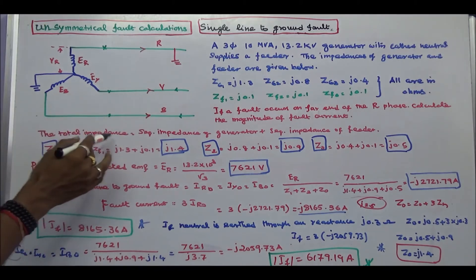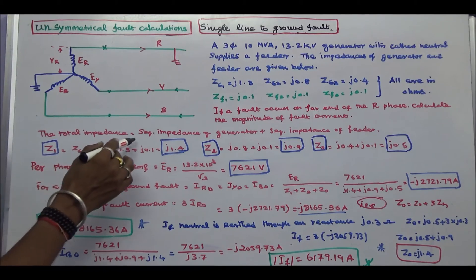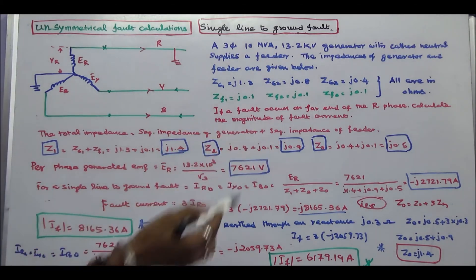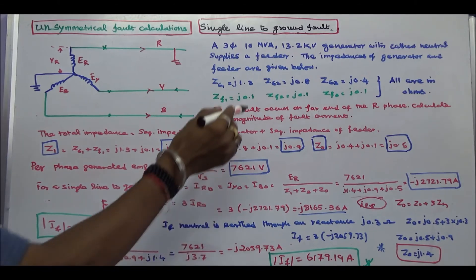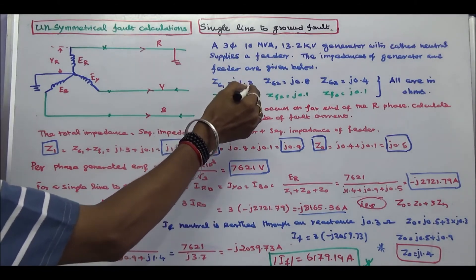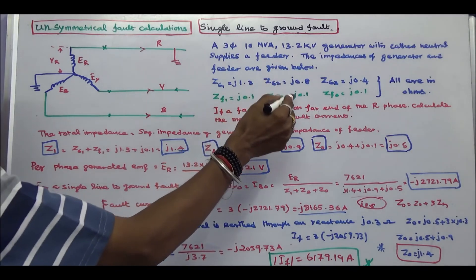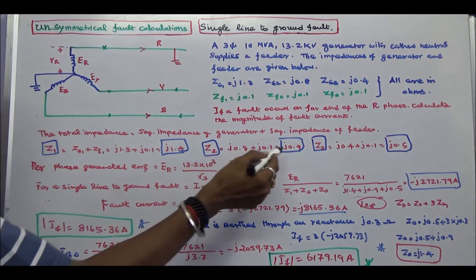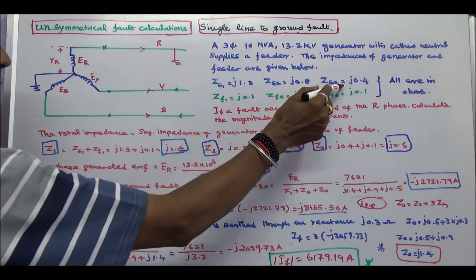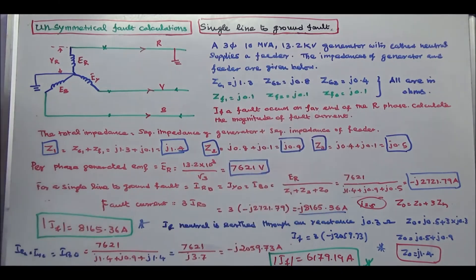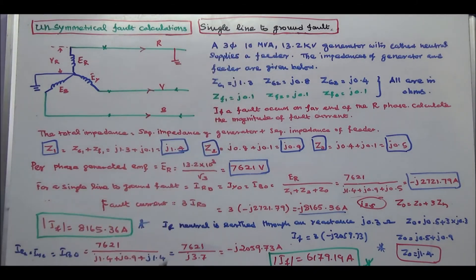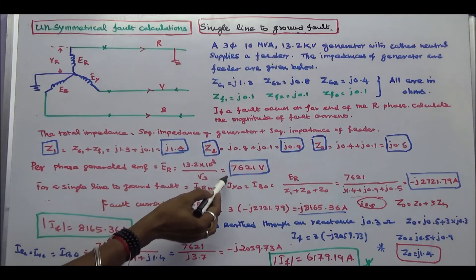First step: calculate the total impedance, which equals the sequence impedance of the generator plus the sequence impedance of the feeder. So positive sequence Z1 is equal to J1.3 plus J0.1, giving Z1 equal to J1.4. Z2 is equal to J0.8 plus J0.1, giving Z2 equal to J0.9. Z0 is equal to J0.4 plus J0.1, giving Z0 equal to J0.5. Next step: calculate per phase generated EMF Er, which is 13,200 divided by √3, equal to 7621 volts.